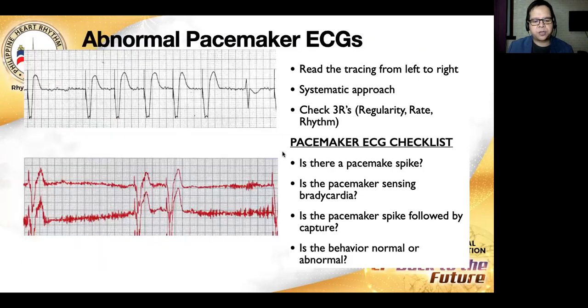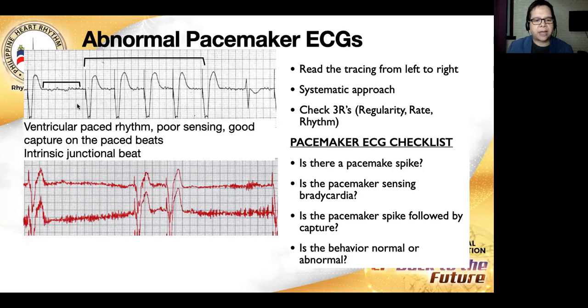More ECG strips here. The first one shows pacing spikes followed by ventricular capture at a rate of 70 beats per minute. But then there is a pause here which is not sensed by the pacemaker, and hence it does not pace. So this is a ventricular paced rhythm with poor sensing and good capture on the paced beats. And there is an intrinsic junctional beat seen here.